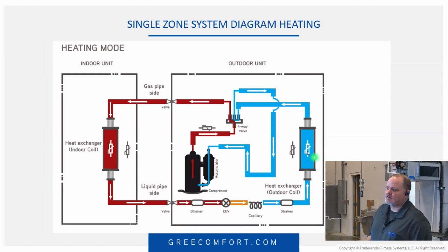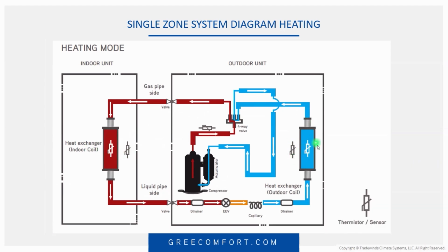It's looking at your outdoor coil temperature. Even in heating mode, it's looking at that outdoor coil temperature. It knows it's got a 10-degree demand in here. It's going to try to absorb as much heat as it possibly can. So it's going to dial the fan speed up outside to put as much load on that evaporator as possible, to try to gain as much heat as possible and then transfer that heat to the indoor coil. So it's all working together.